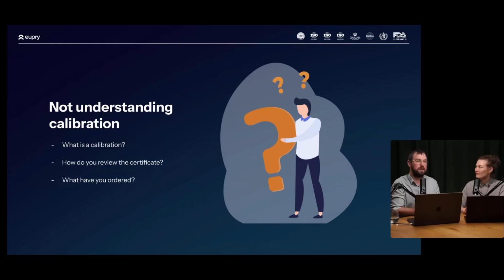What's on a certificate? The fortunate situation is that ISO 17025 very clearly describes what should be in a certificate. It can be in a lot of different ways, of course, but the minimum amount of information in a certificate is mandated by 17025 in very decisive terms. So you need to have that understanding of what it actually is you're looking for, and then lastly, what have you ordered? This comes back to setting your calibration requirements. What did you actually order?